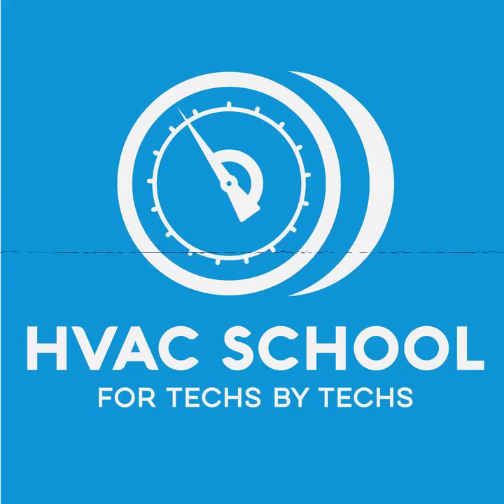So what is commissioning? Commissioning is making sure that the equipment is working appropriately as the manufacturer specified and as the application specified. I'll give you another example. In Florida, where we live, high relative humidity, we design systems to run about 350 CFM, cubic feet of air per minute per ton, as opposed to 400 that you see around the rest of the country.